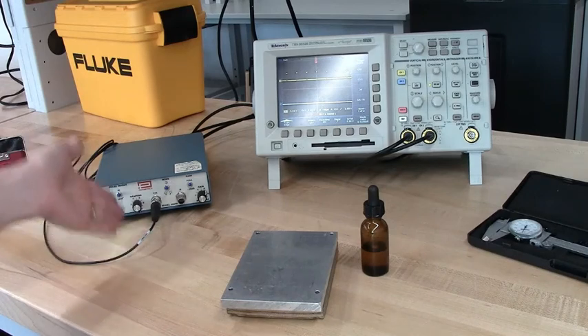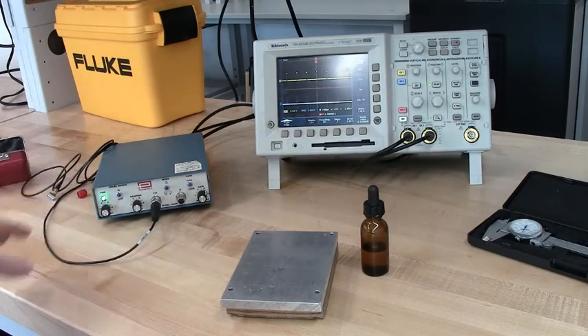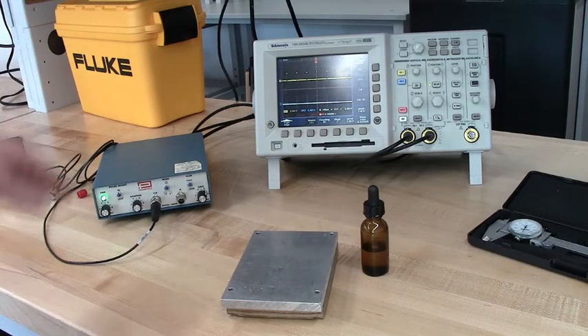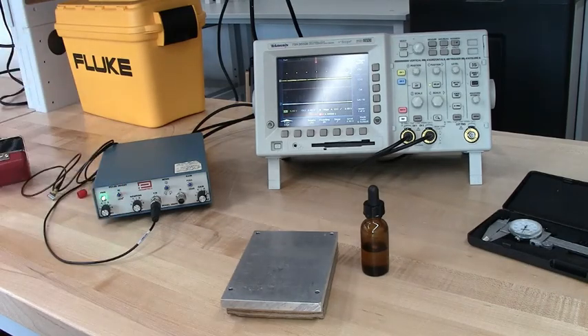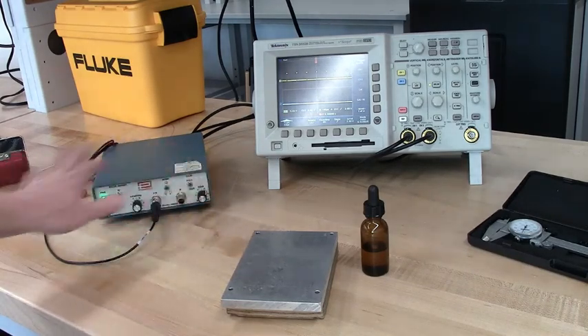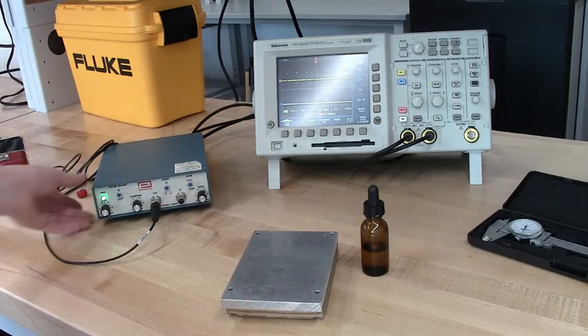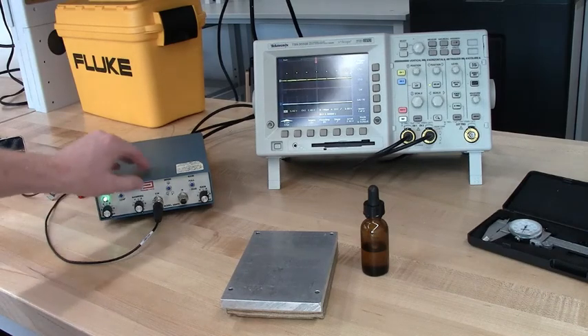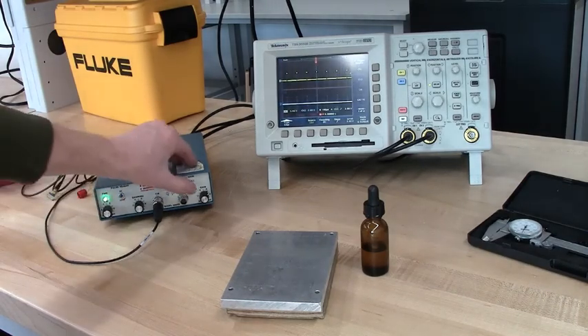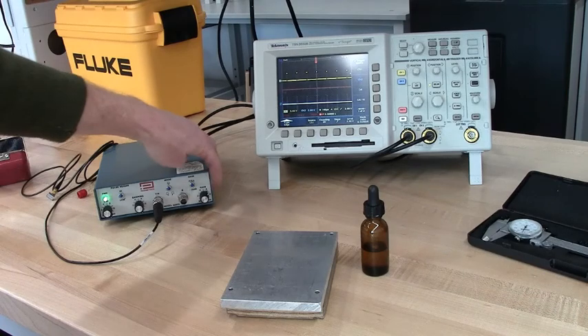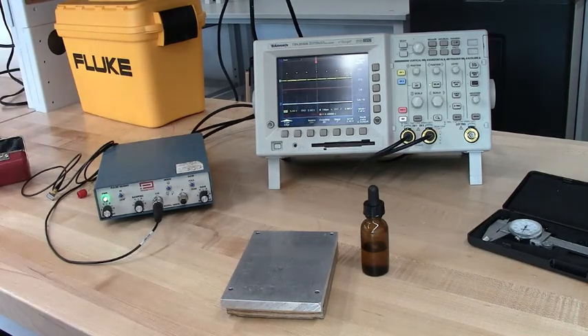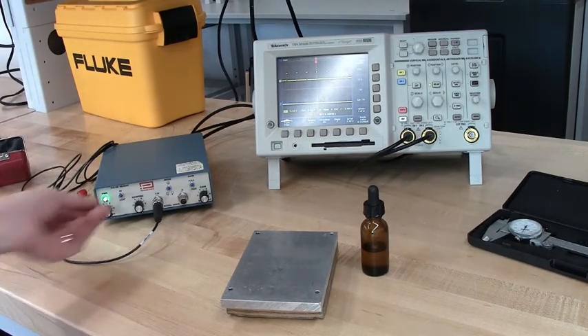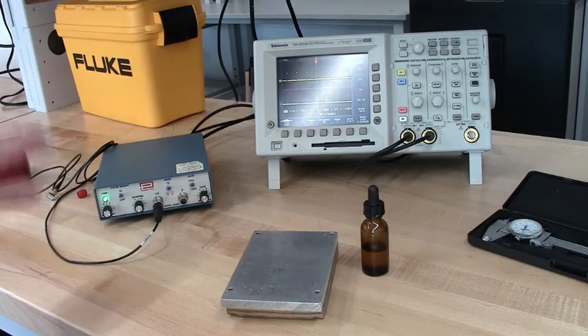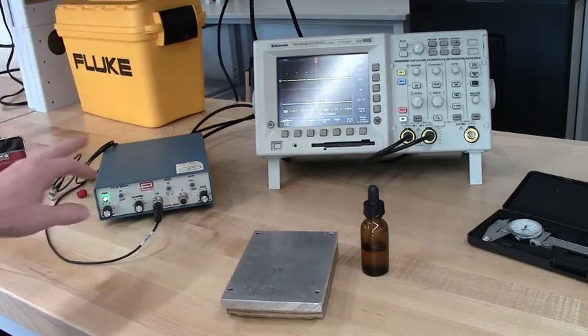Some other settings on here are the damping. We have a pulse height high, a gain, either the full or a minus 20 dB cut on it, and we have a gain setting here too. Most of that stuff we'll just keep on max. I guess the pulse height's on high, the gain is on full. Our gain is on 6 out of 10 right now. That should work well. The damping is on high. We can adjust those a little bit when we zoom in to see.